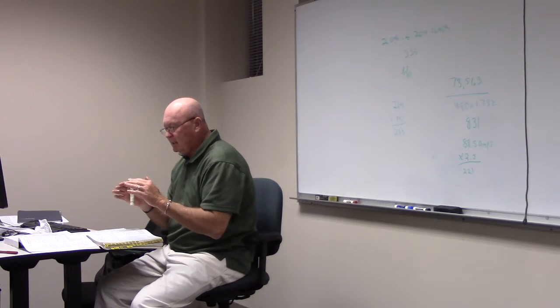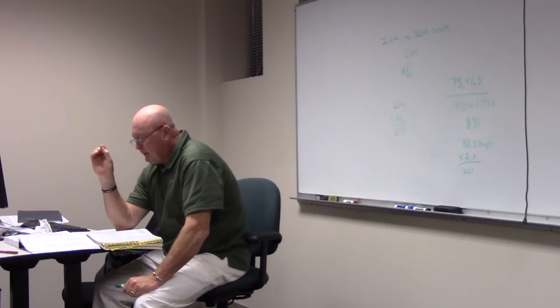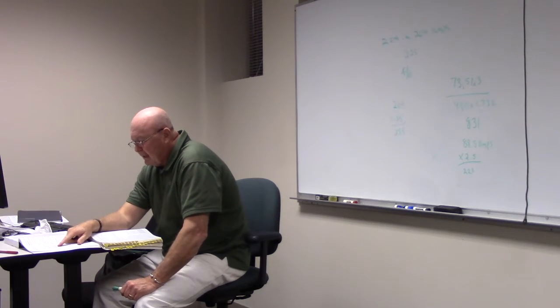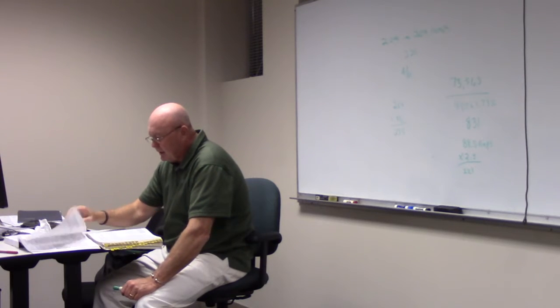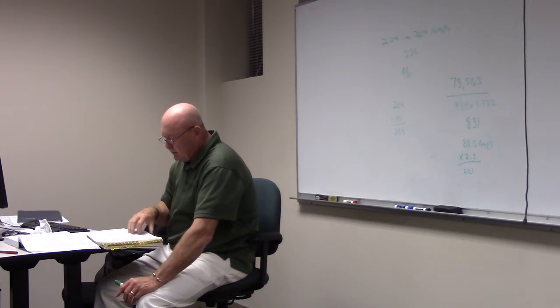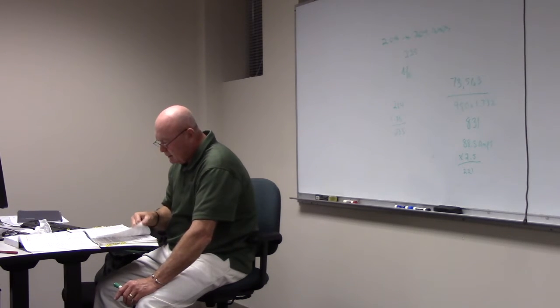Now we've got to do the primary, the 480. And if we do this, we're going to call it a night. Okay, we're done. So look at the primary feeder, which is the 480 we were trying to figure out. Now for the feeder calculation, let's start with the lighting load. So we're back to our example here. We see that it said what, 20,000 square foot? Okay, 20,000 square foot, so we have to go back and find what kind of multiplier we're going to use for this.